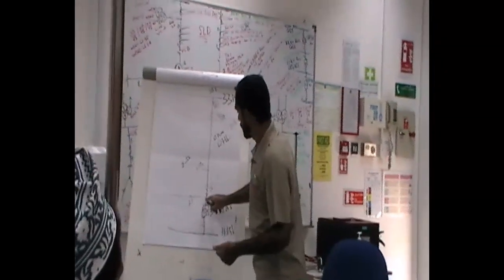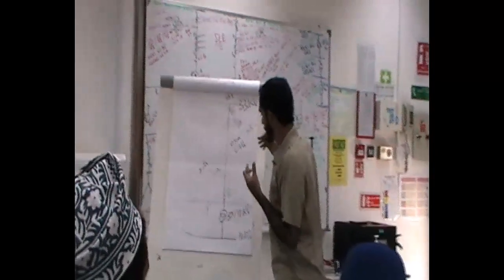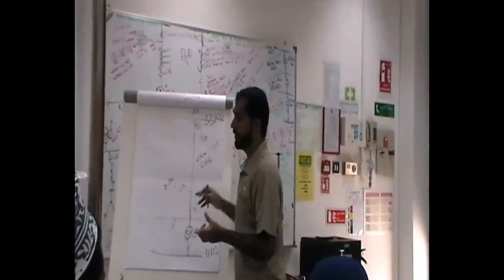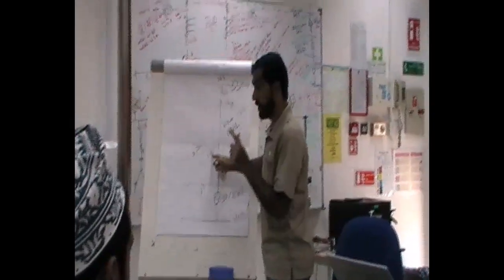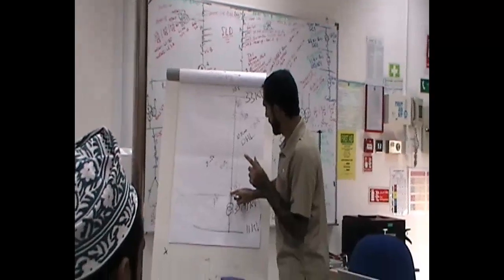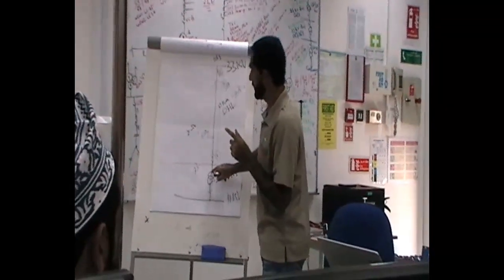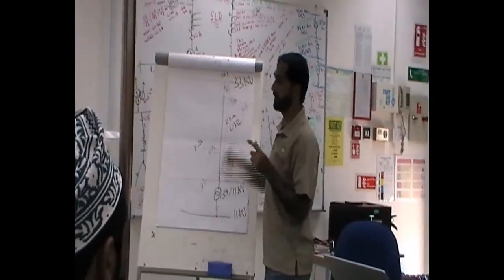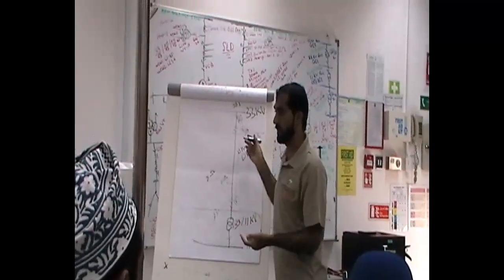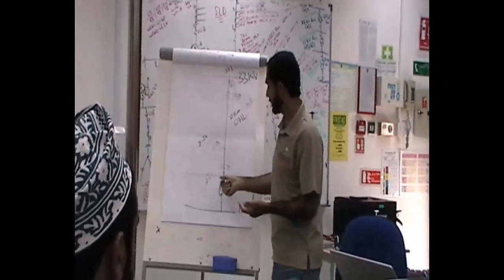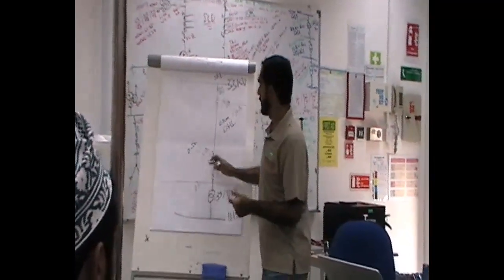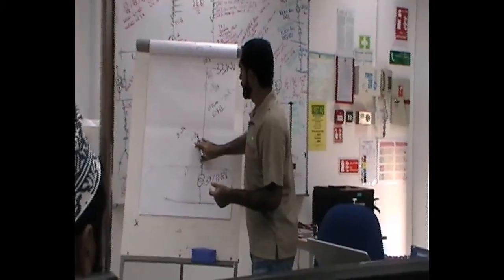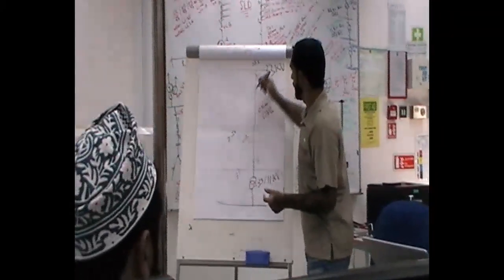But I cannot go up to here because the precise reading is difficult. So if I extended zone 1 with 0 tripping up to here, the fault could be at least here, and it will trip the whole line. I have to search the whole line in this case to find the fault, and the fault is in this substation. So zone 1 only up to 80 or 85% of the line.